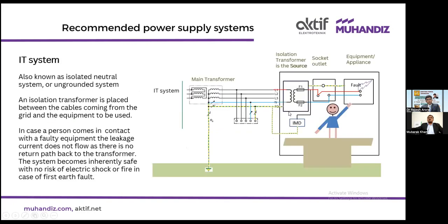Now, what is the solution? We have discussed the problem. The solution is using the IT system. Now, what is the IT system? Just to explain very briefly, I have simply introduced one small isolation transformer before our socket outlet. In the earlier case, the neutral of the transformer was grounded. Here, the neutral of the transformer is not grounded. It is a floating neutral system.